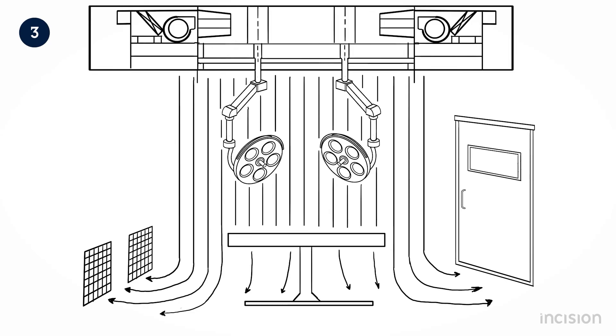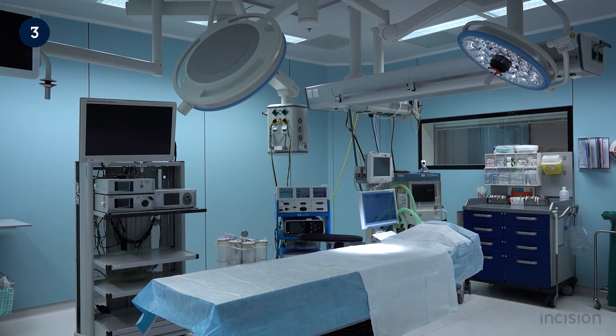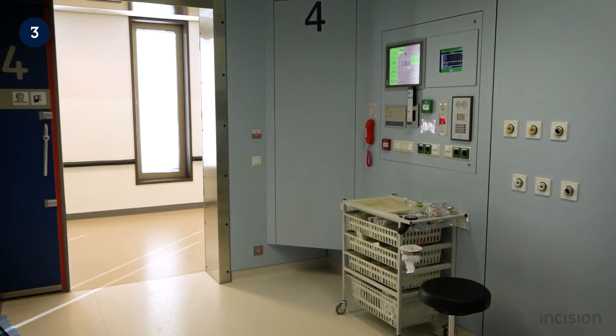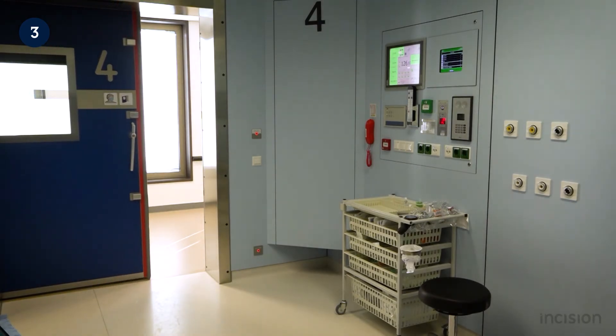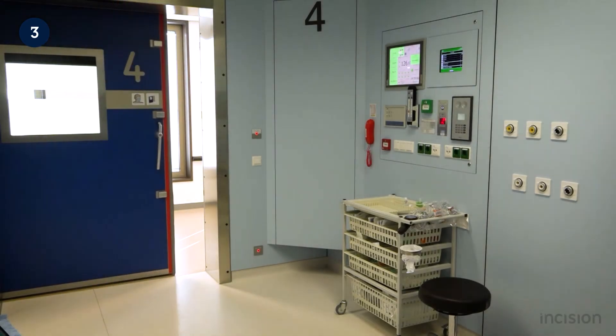These filters are high efficiency particulate air filters, known as HEPA filters, used to remove particles present in the air. The operating room should have a minimum of 15 total air exchanges per hour. Doors to the operating room should be kept closed in order to maintain correct ventilation airflow and pressure.